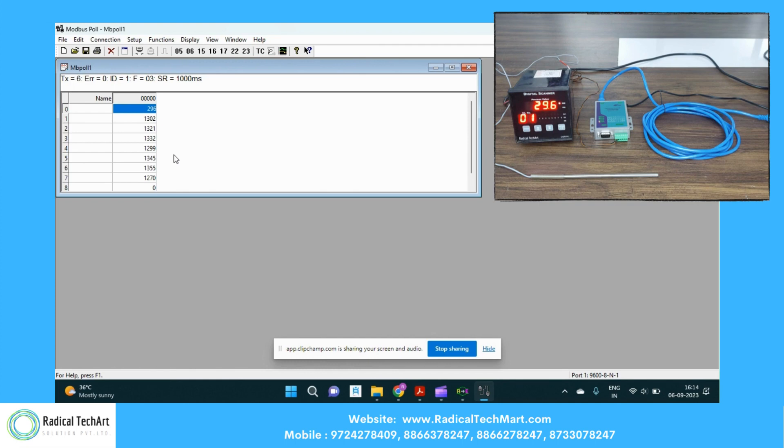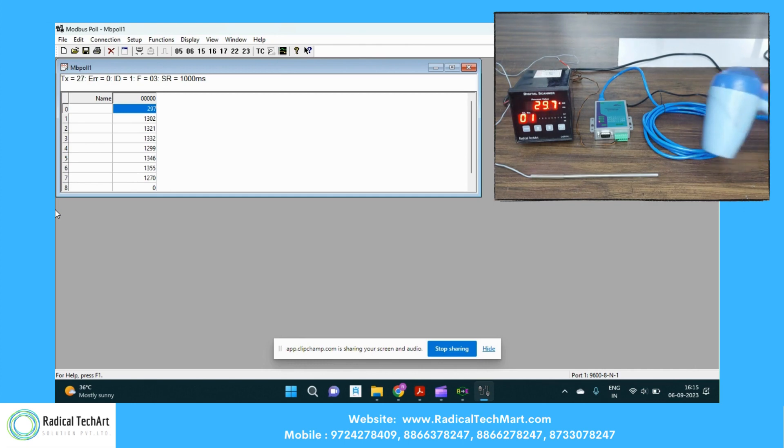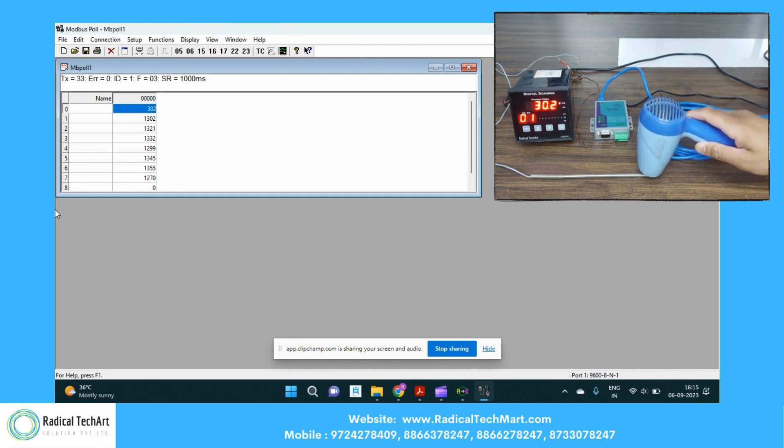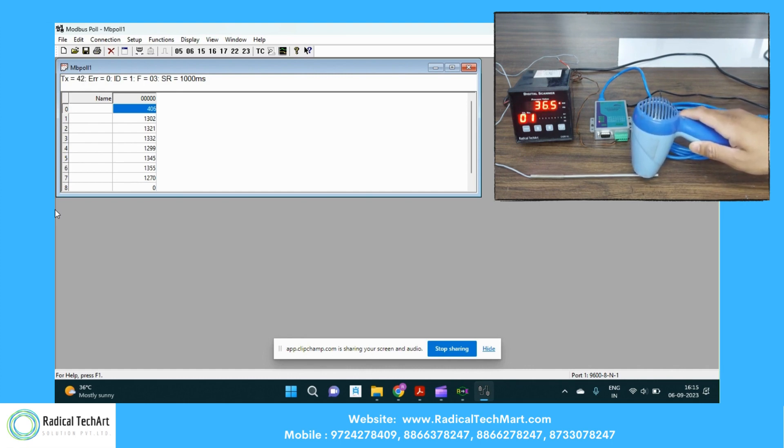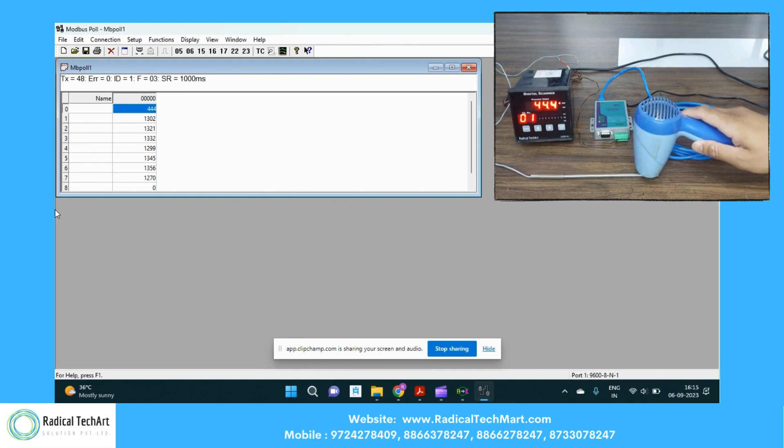You can see on the screen we have already done the setup. Here we have the temperature sensor, which has a reflecting the temperature indicator. Now I'm going to increase the temperature with the blower. If you look at both of the screens, the temperature is keeps increasing on the channel number zero. So we have now 30.2 and now it is keep increasing 36.5. You can clearly see that on the temperature indicator and the Modbus poll software that it keeps increasing.